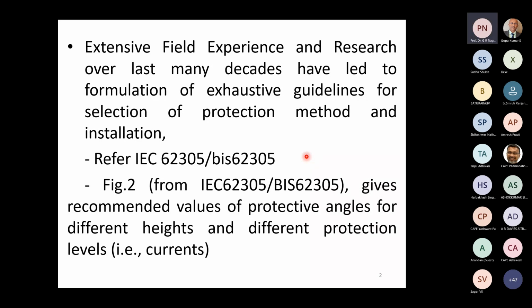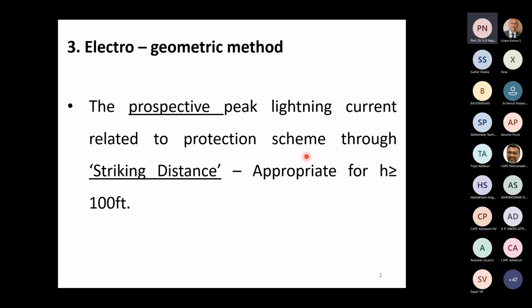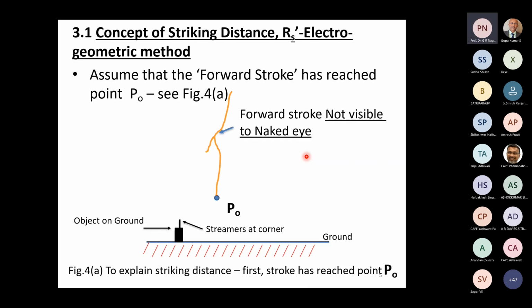We have already stated these things. Now we will come to what is called the electro-geometric method, which involves both a geometry and an electrical parameter, essentially the current in the lightning. We'll see that the prospective peak current in the lightning stroke is related to the protection scheme through what's called the striking distance, appropriate for heights greater than 100 feet. If the height is less than 100 feet, we don't have to worry too much about this electrogeometric method. The simple geometric method we discussed till now, the semi-conical angle of some angle theta, is quite valid. Now, what's the basic principle of this electrogeometric method?